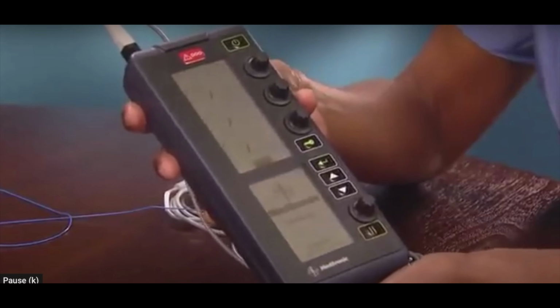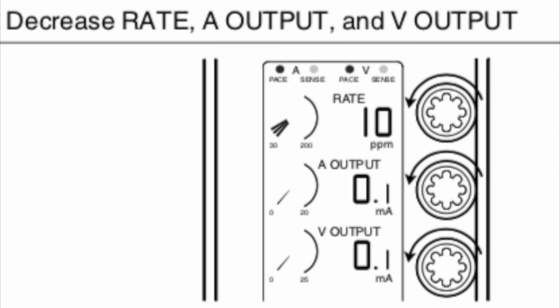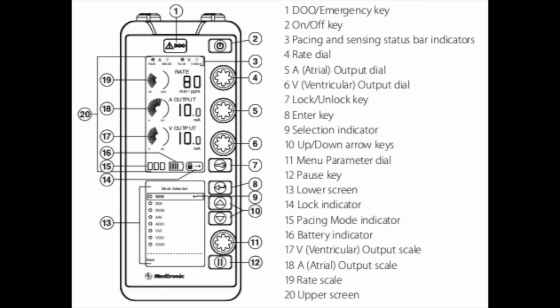Warning: to prevent pacing into the vulnerable period of the T wave, turn on the temporary pacemaker and turn down A output and V output to the minimum amplitude before connecting the temporary pacemaker to the patient's lead system. Determine sensing thresholds before turning up A output and V output to threshold levels.